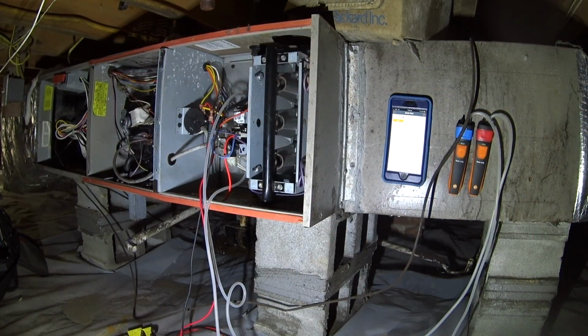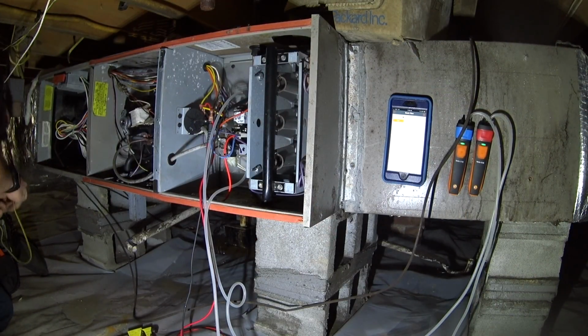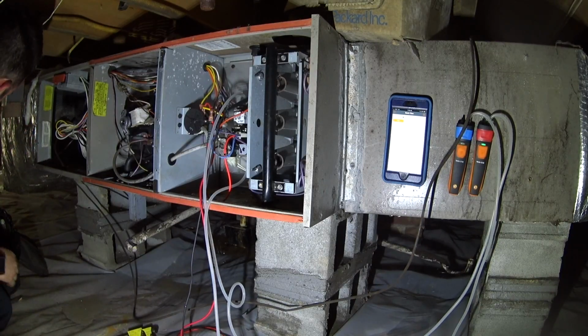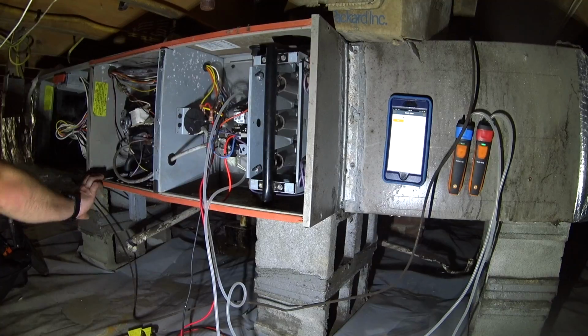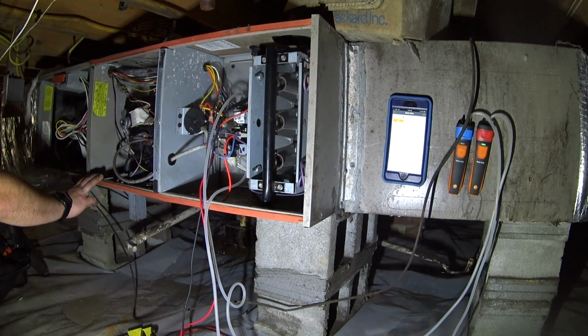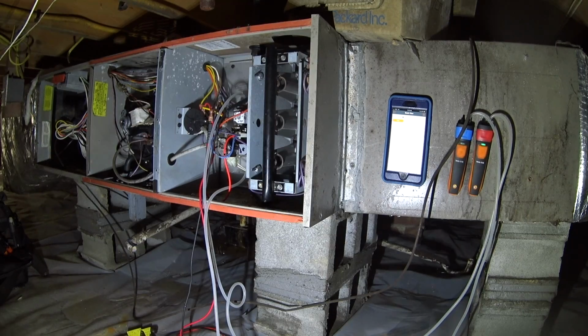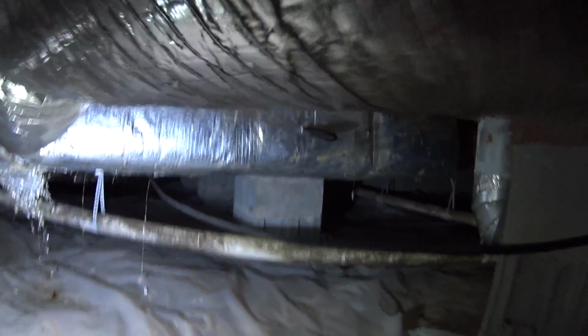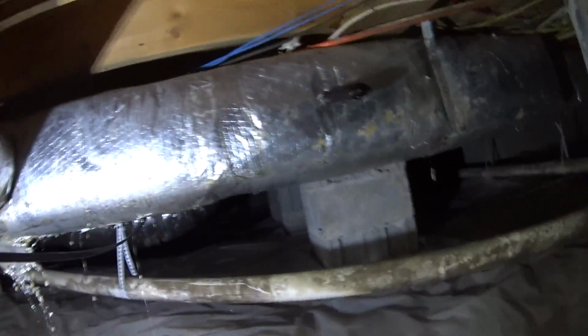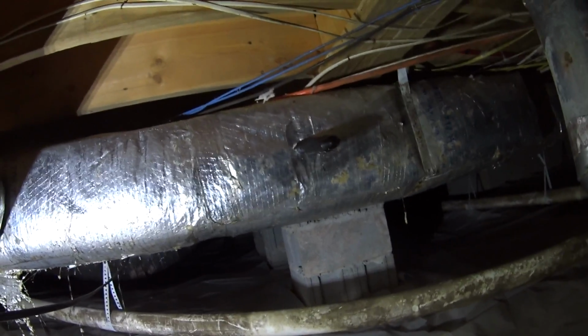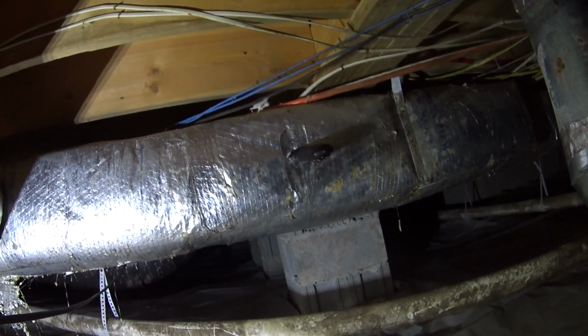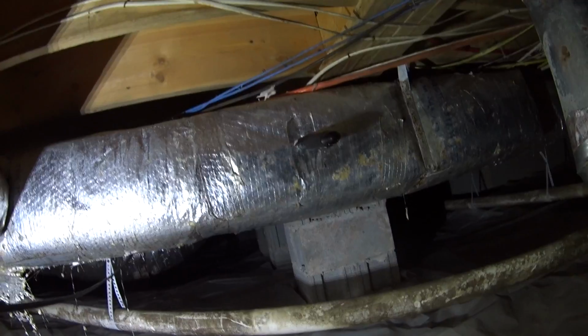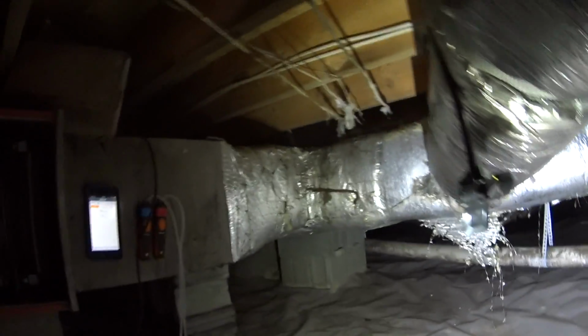We got gas pressure, and I'm going to fire it on first stage to start. So we're going to get the combustion analyzer ready and the iManifold probes in place. As far as using iManifold for heat checks, basically all you need is the air probes and either the iManifold box or the iConnect box. We've got the supply air probe over here, down and around the corner from where the furnace heat exchanger is, and then we've got the return air probe down here.